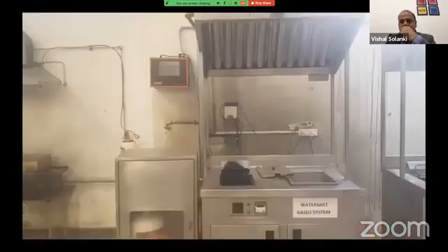As you can see on your screen, the temperature has reached 43°C. That is the beauty of water mist. The water mist really cools the fuel down. There is no chance of reignition post this. So let's wait for the fire in our domestic kitchen.